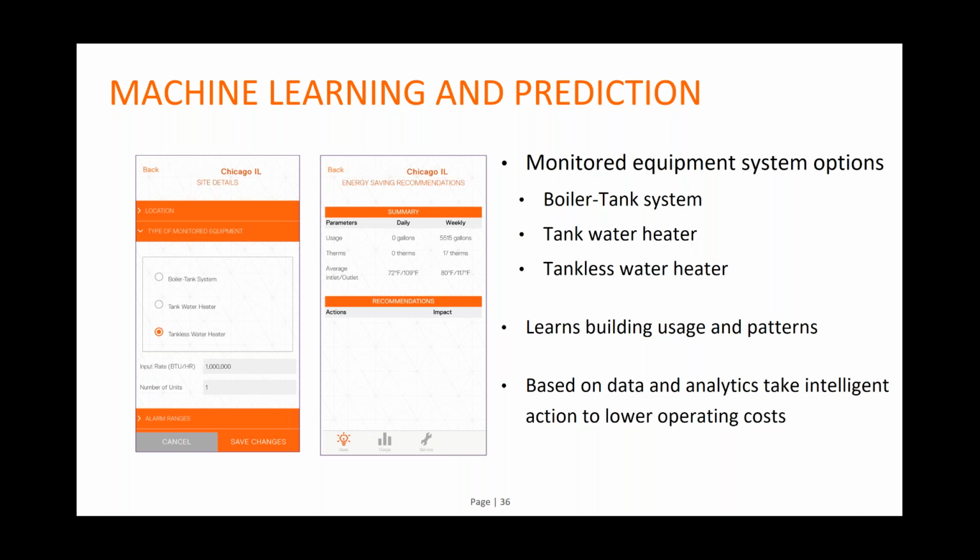So we do that extremely well. Great. And generally we find, this is a very general statement, equipment is terribly mismatched for the building. I mean, they are usually on the opposite end. If a building might need 3 million BTUs, usually we'll find 6 or even 9 million BTUs. Wow, yeah. It's a common problem, I think, isn't it?